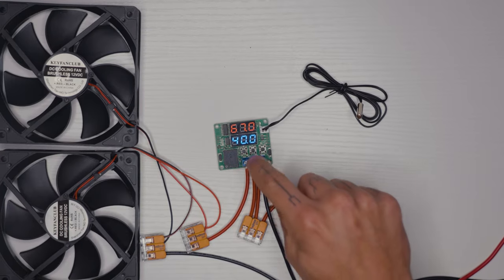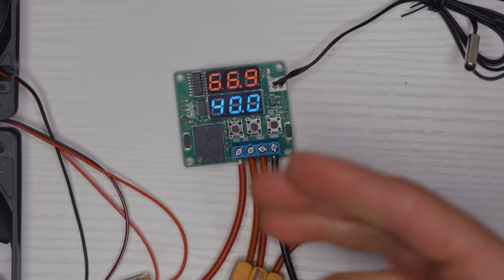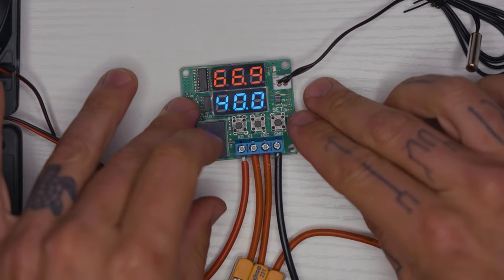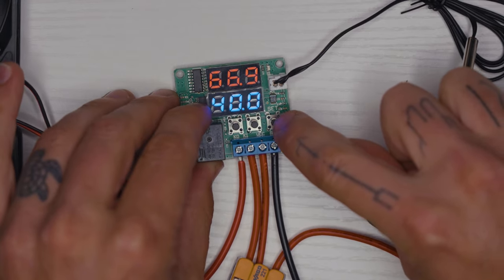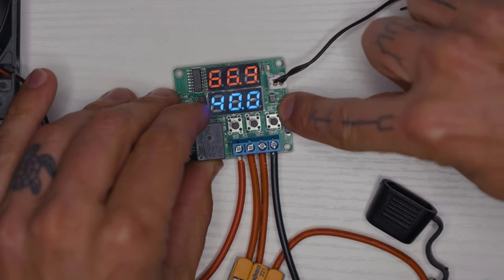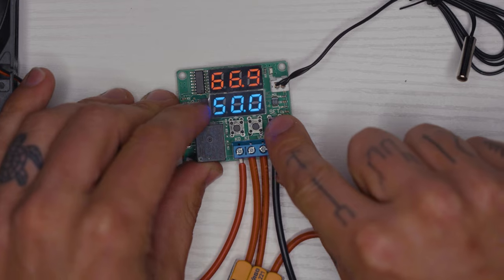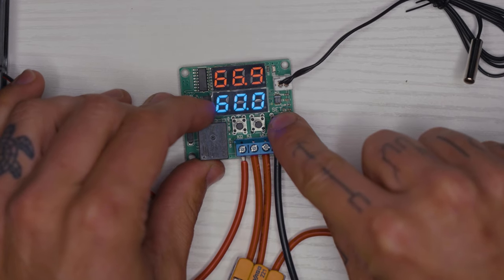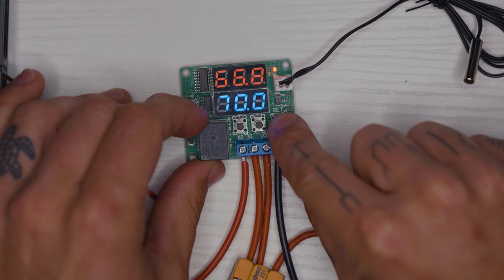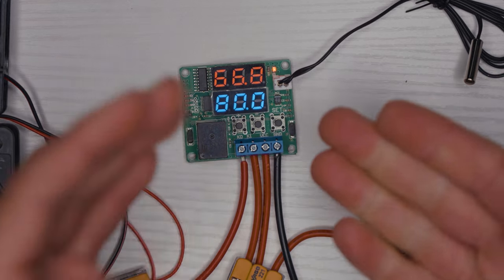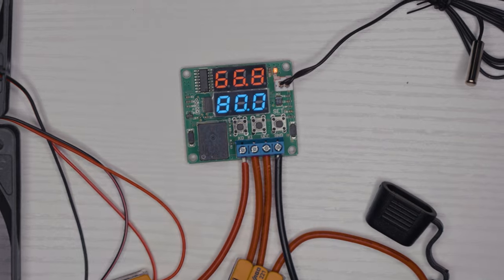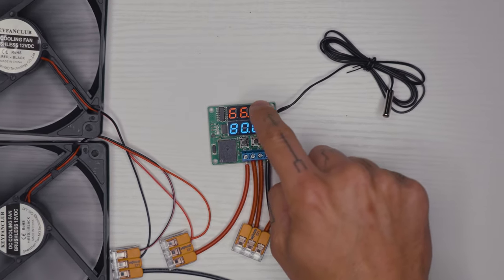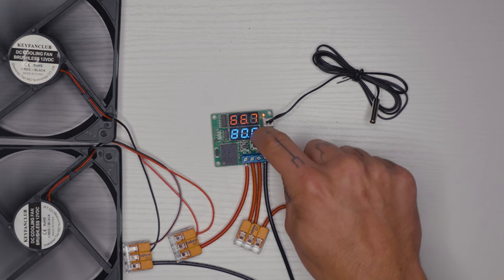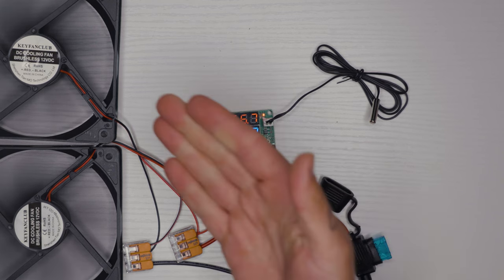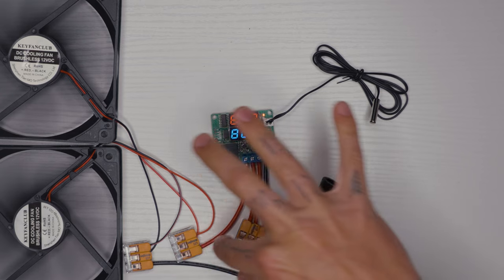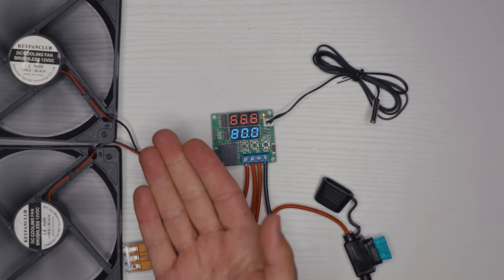Now for programming, there are three buttons right on top. To set the programming for this, we simply push the one that says set right here on the far right side until this bottom changes to the level that we want it to change to. So we'll set it to 80 degrees. Now it's 66.8 degrees in here right now. We've just set this to turn on when it gets to 80, but the fans are on, which means this is a reverse function of what we actually want it to do.